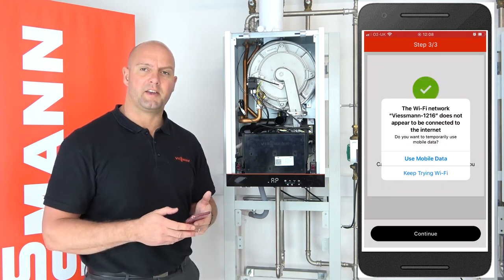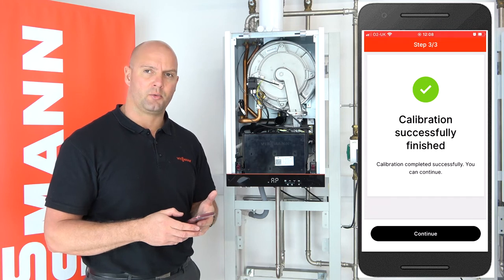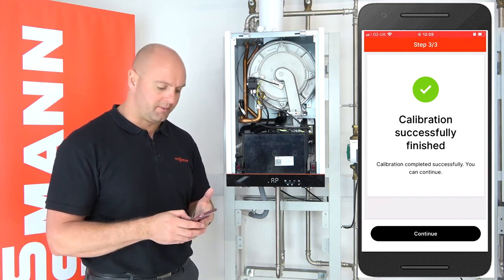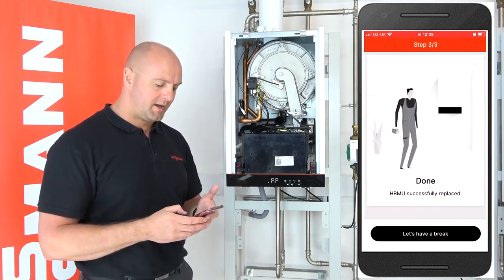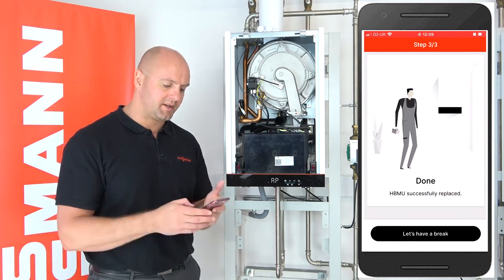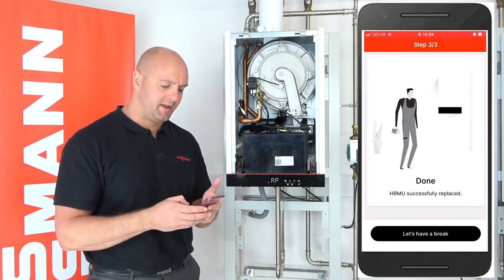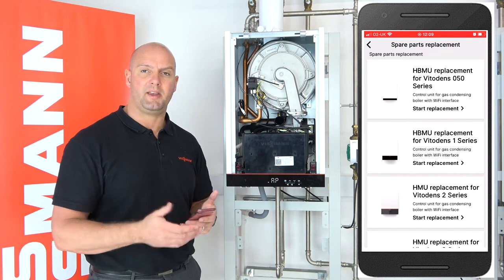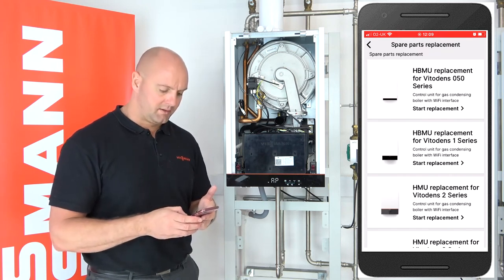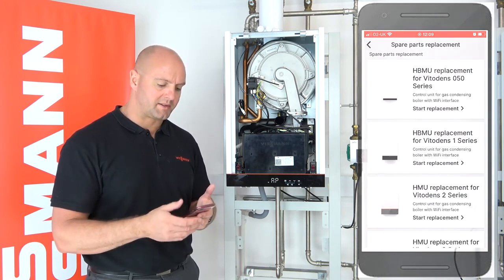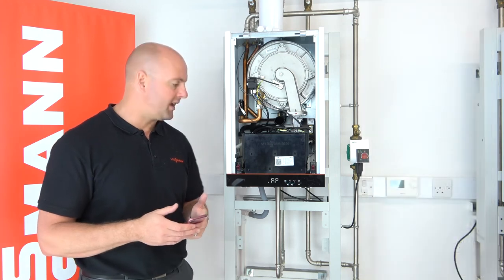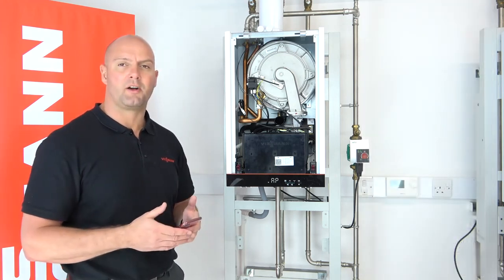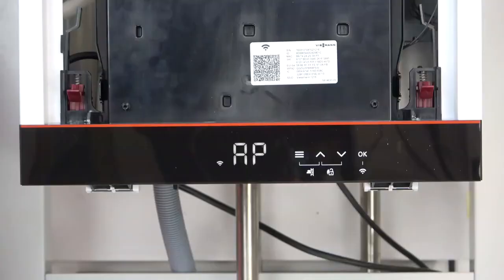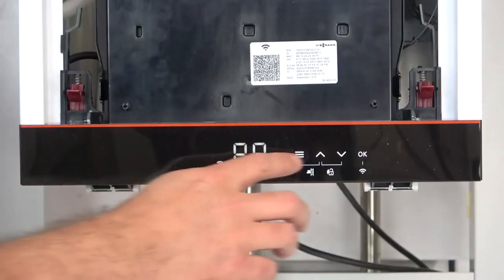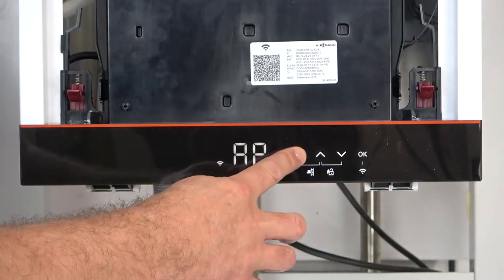If you get a notification to use mobile data or continue using Wi-Fi, always select keep trying Wi-Fi. As you can see now, the calibration is successfully finished, and that's our PCB now calibrated. We follow it through and we're back to the main screen on the app. You will hear the boiler start up again, and I've just heard the pump come back on. You can see now it's completely finished and the boiler is still in AP mode.